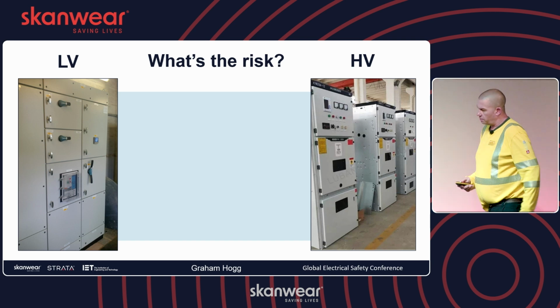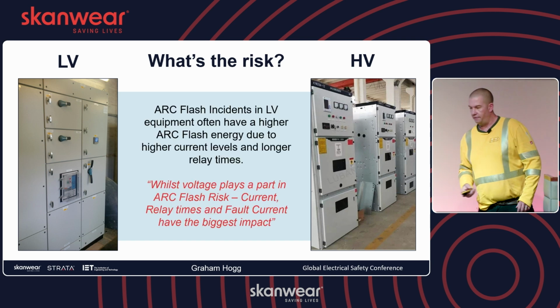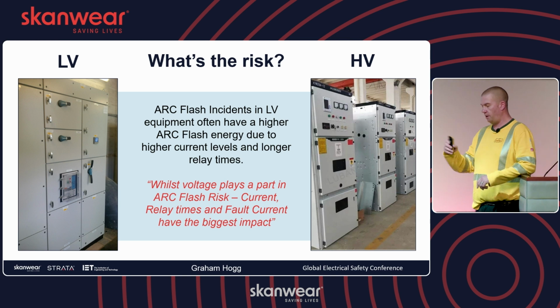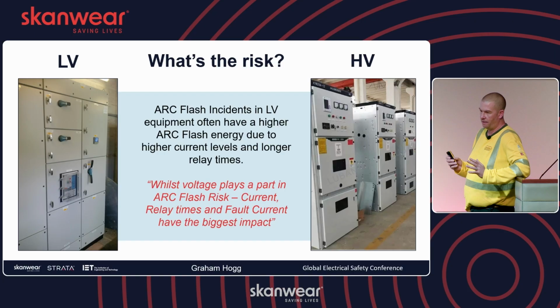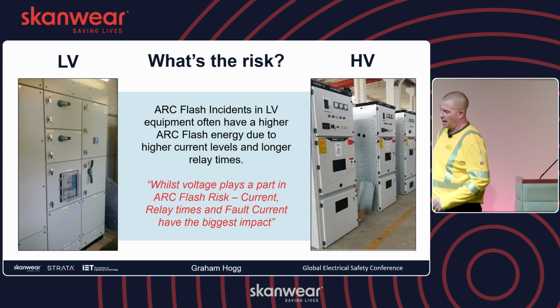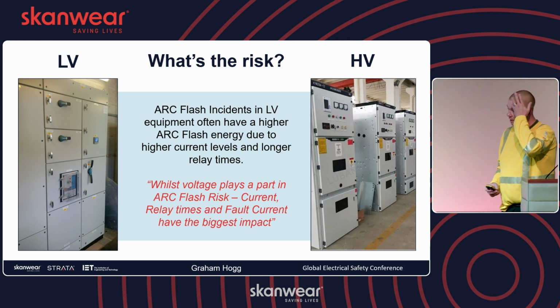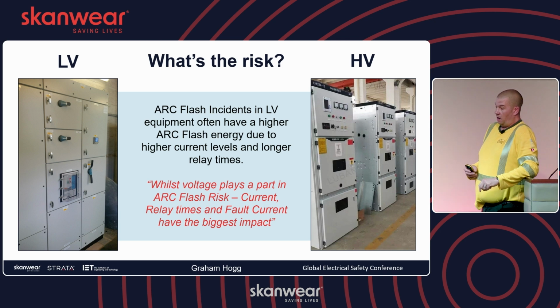So what's the risk? We've got HV and LV, and I've heard a lot spoken about HV over the past day and a half, and yes it's a high-risk environment, but when it comes to arc flash, LV is generally where you're going to have the larger available energy, due to the longer tripping times, we've got a higher current, and for me, likelihood, there's a lot more LV gear out there.